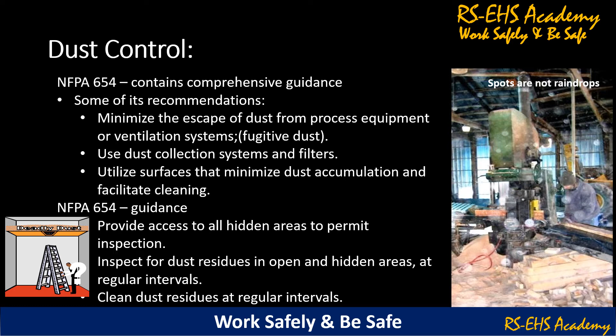NFPA 654 guidance also includes: provide access to all hidden areas to permit inspection. Inspect for dust residue in open and hidden areas at regular intervals, and clean dust residue at regular intervals. Dust control as per NFPA 654. Use cleaning methods that do not generate dust clouds if ignition sources are present. Only use vacuum cleaners approved for dust collection.